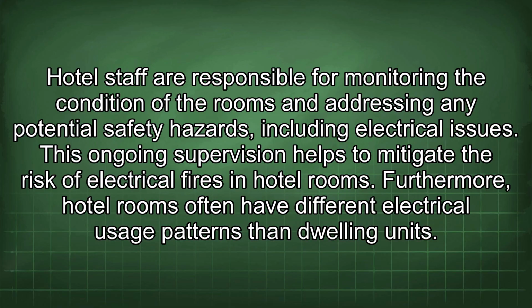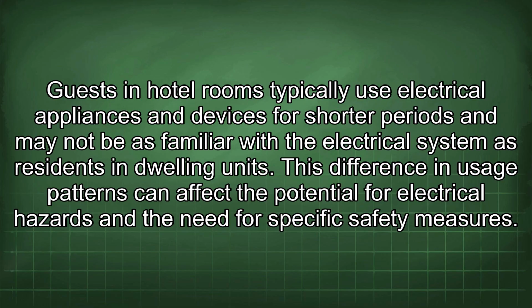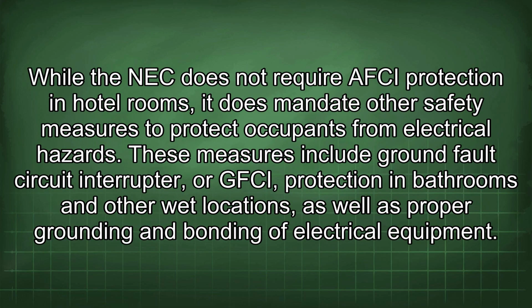Furthermore, hotel rooms often have different electrical usage patterns than dwelling units. Guests in hotel rooms typically use electrical appliances and devices for shorter periods and may not be as familiar with the electrical system as residents in dwelling units. This difference in usage patterns could affect the potential for electrical hazards and the need for specific safety measures. While the NEC does not require AFCI protection in hotel rooms, it does mandate other safety measures to protect occupants from electrical hazards. These measures include ground fault circuit interrupter, or GFCI, protection in bathrooms and other wet locations, as well as proper grounding and bonding of electrical equipment.